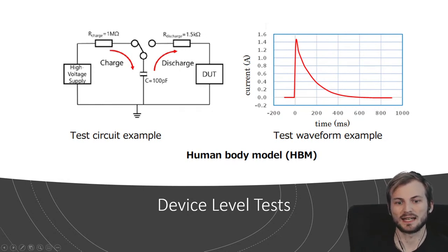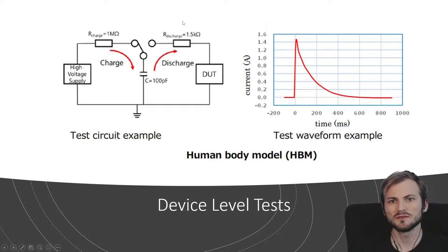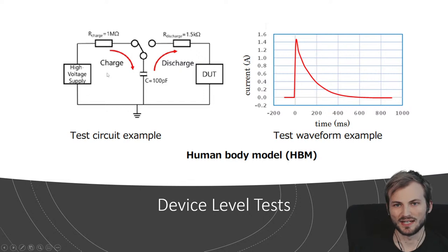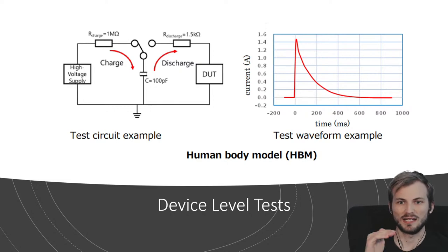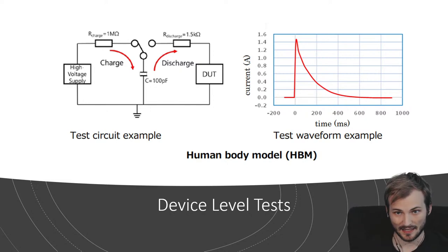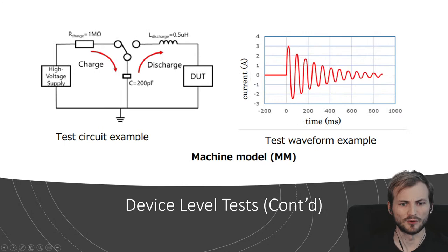For the actual test there are specific values for the voltage, but they won't specify what the voltage is here, because there's a specific standard which specifies what voltage is used. The way these are tested, for both the device level and system level tests, is you start at a low voltage and keep stepping it up until it eventually fails, then you can say it passed at the level right below that. That's why you don't see any voltages listed.